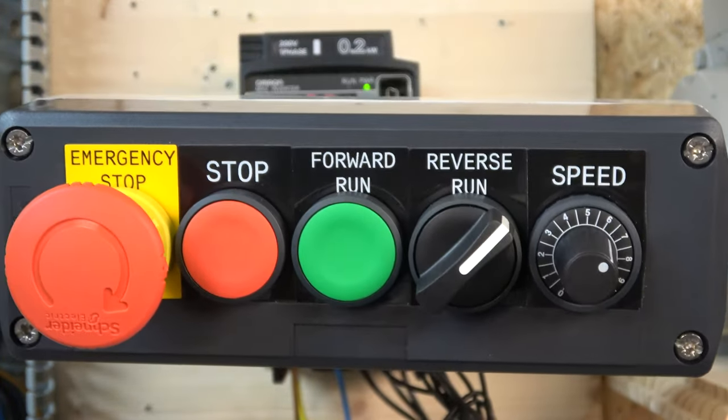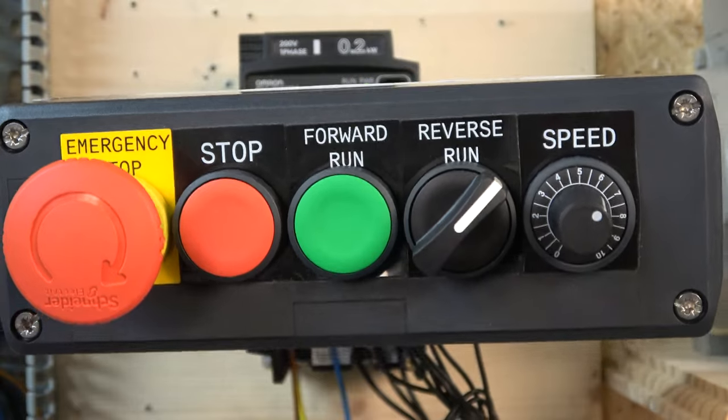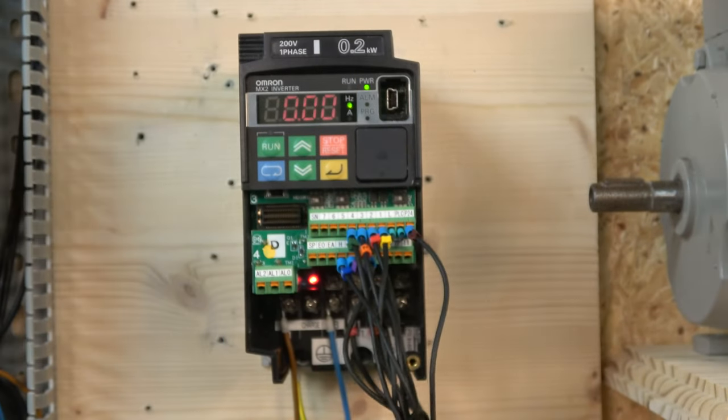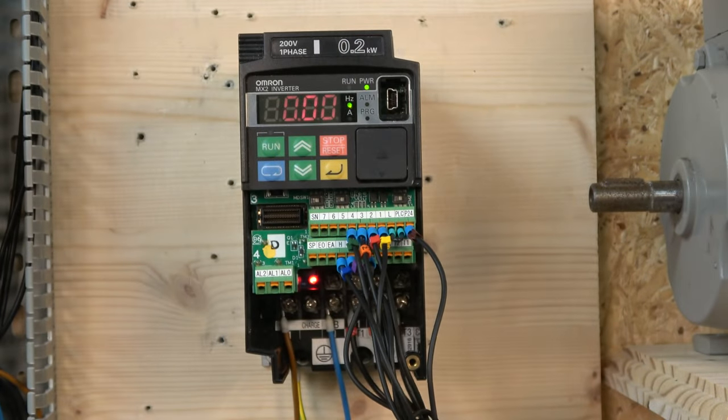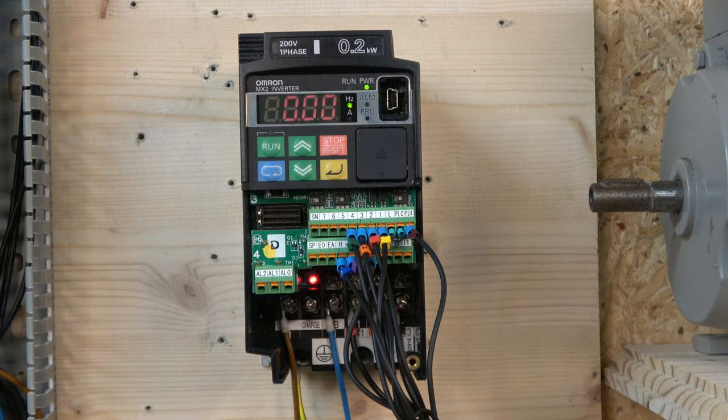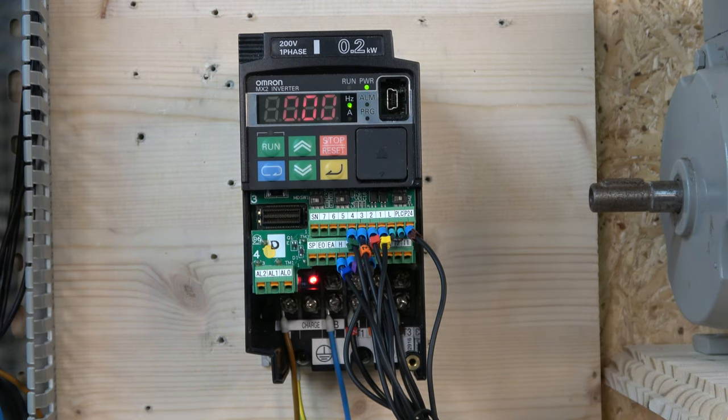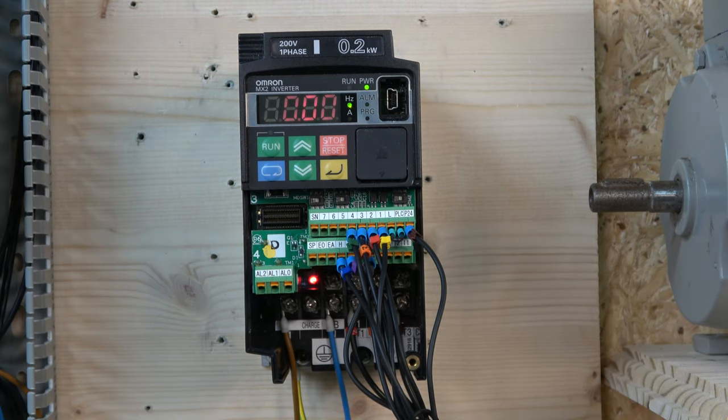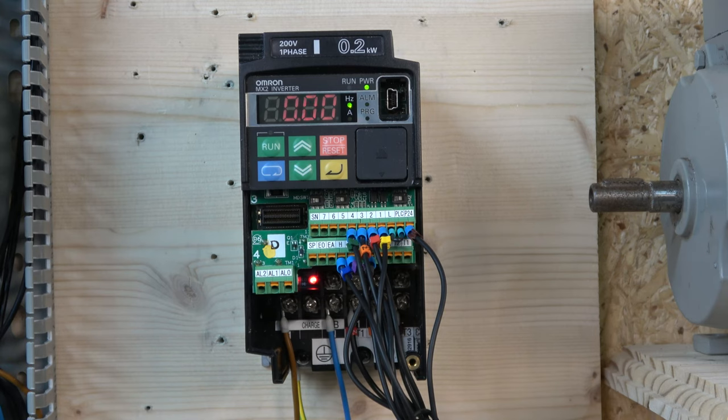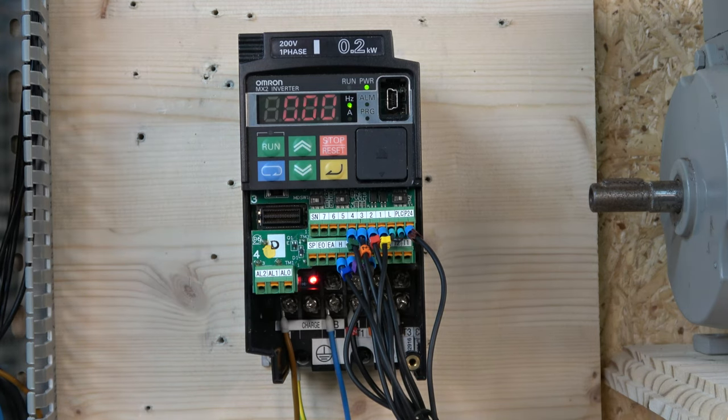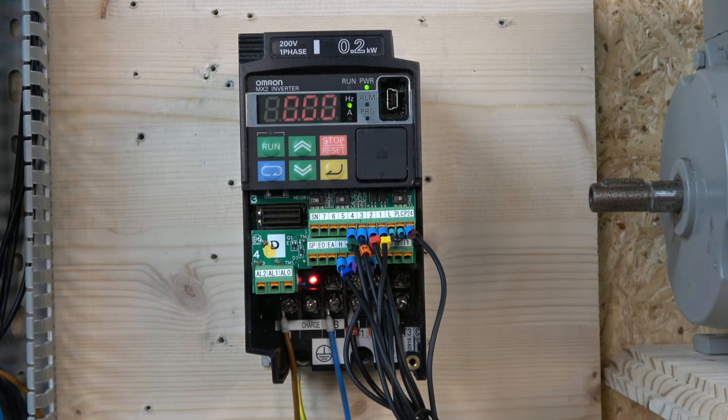Look what happens when you are in an emergency. There we go, driver motor goes completely in free run, it isolates the output and it's pretty much doing nothing. So once you release it, it will request you to reset the drive. All you need to do in here, click the reset button on there and it will reset it. And you can have external reset button to your station if you wish so you can do that as well. It's depending again on your application. Remember all those inputs are highly configurable to wherever you like. And Omron has, as I say again, did not get shy about giving you options for pretty much whatever you can come up with.